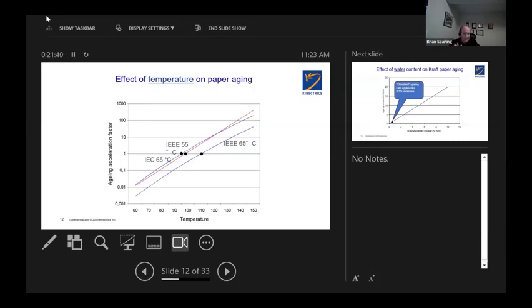So IEEE 65 is the standard that transformers are built mostly to in North America. 65C is the average winding rise, maximum average winding rise at a winding's hotspot temperature of 110 degrees C. If you can hold the transformer at the winding temperature of 110 degrees C for 24 hours, constantly, no change, it has an aging acceleration factor of 1, meaning it has aged 24 hours within that 24-hour period. Aging acceleration factor of 1. You can see that this is a log scale. So for every 7 degrees C above that 110 degrees C, the aging acceleration factor doubles. That goes from 1 to 2, just by an increase of 7 degrees C in winding hotspot temperature. Likewise, 7 degrees C less than 110, the aging rate is halved and continues to be halved as the winding temperature goes down. So that's the impact of temperature on the paper.